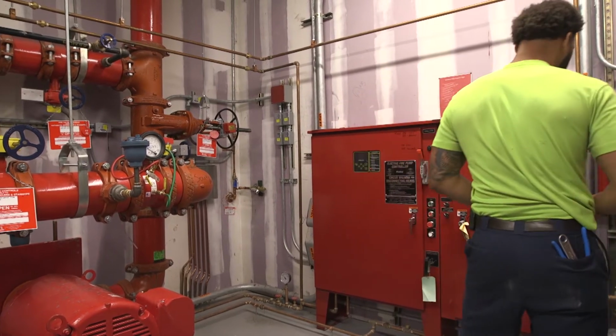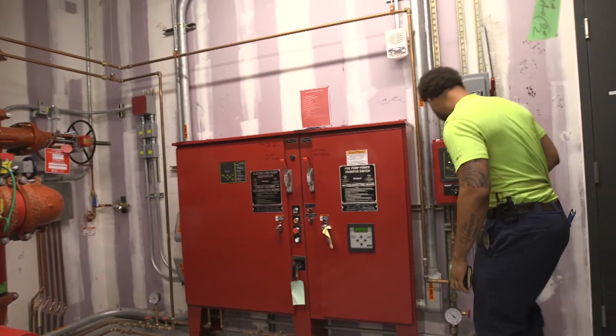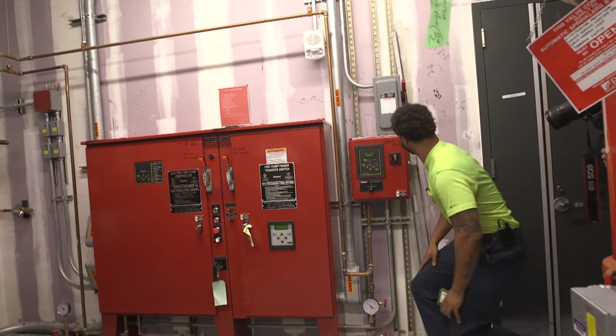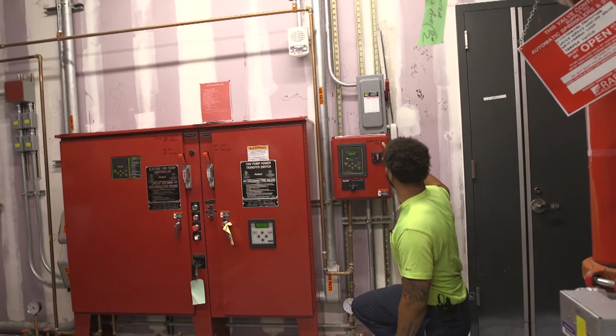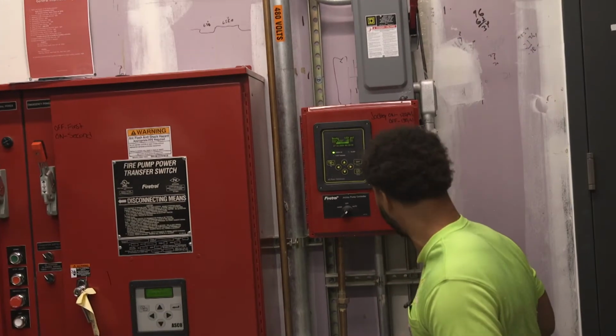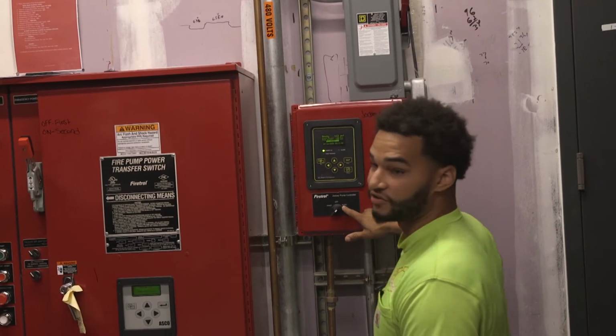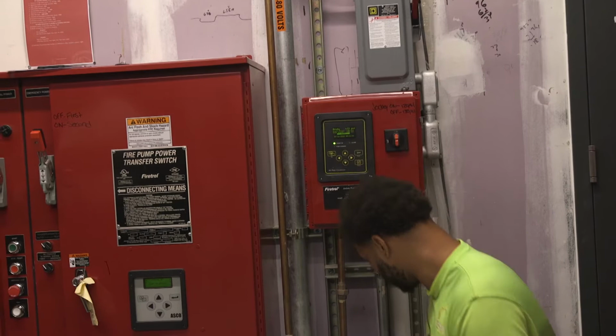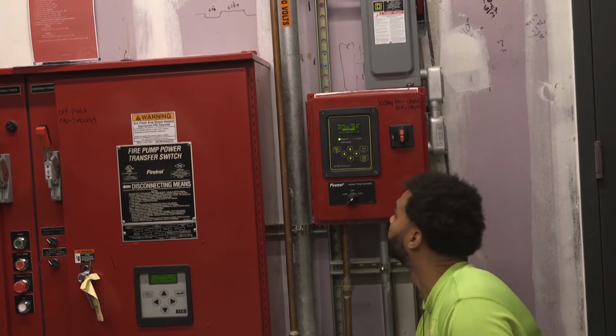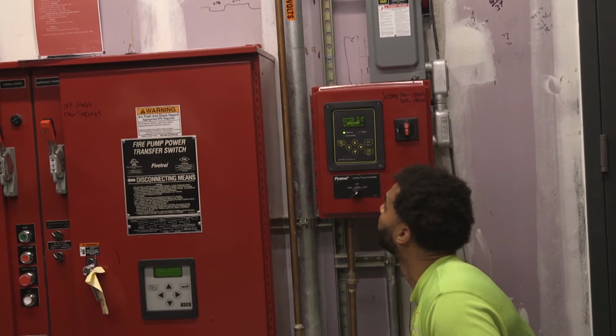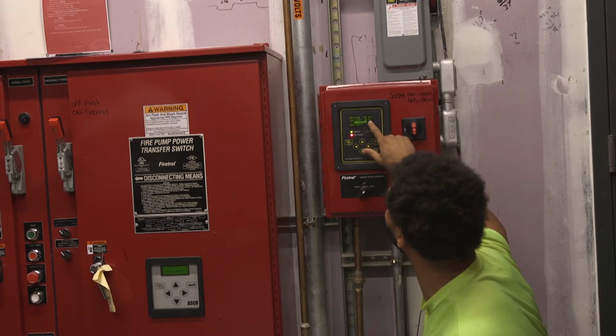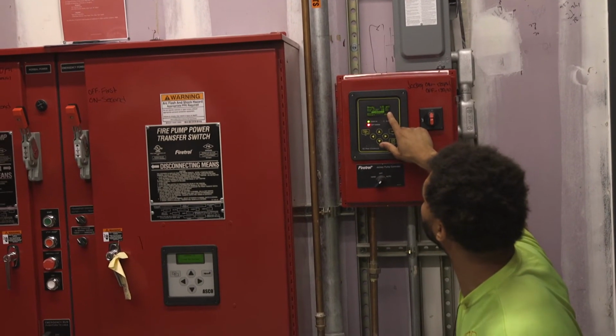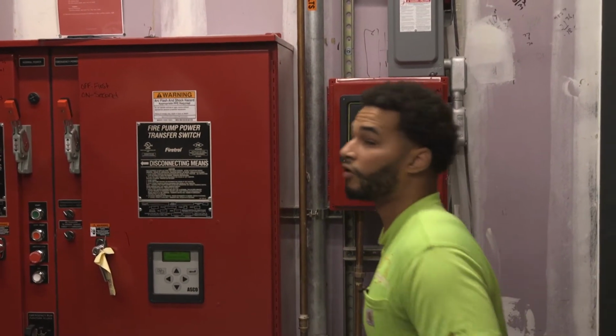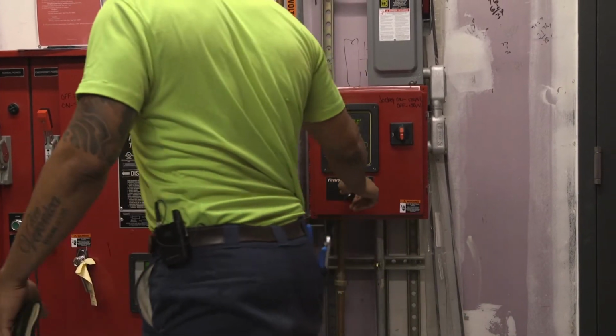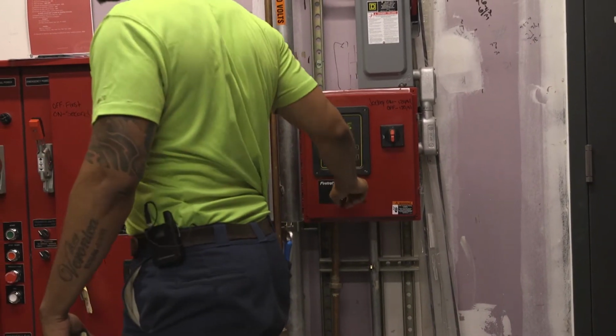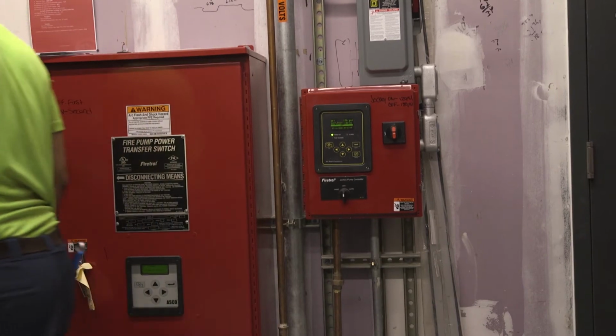So first thing, we'll come over here to the jockey pump. So we'll be looking at our screen here. So our jockey pump is going to kick on at 120 and it's going to kick off at 130. Our jockey pump is always to be set in the auto position. There it goes. And there it goes. So we're good. So now we're going to switch the jockey pump to the off position.